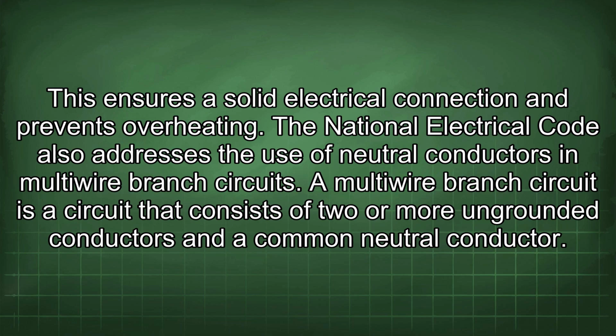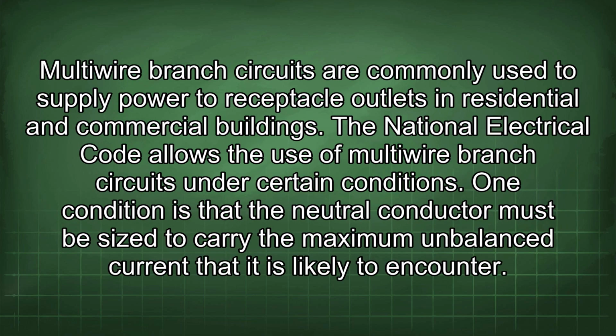The National Electrical Code also addresses the use of neutral conductors in multi-wire branch circuits. A multi-wire branch circuit is a circuit that consists of two or more ungrounded conductors and a common neutral conductor. Multi-wire branch circuits are commonly used to supply power to receptacle outlets in residential and commercial buildings. The National Electrical Code allows the use of multi-wire branch circuits under certain conditions. One condition is that the neutral conductor must be sized to carry the maximum unbalanced current that it is likely to encounter.